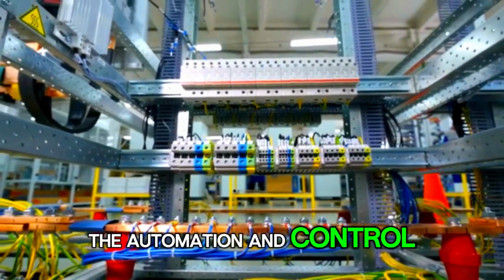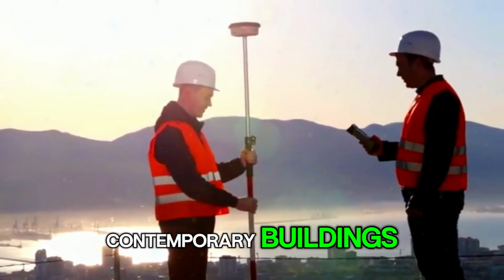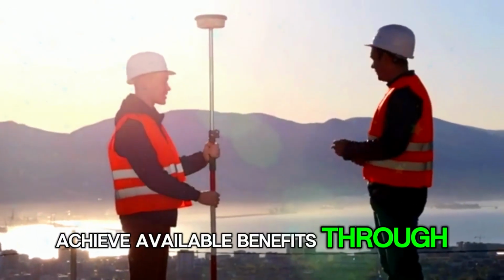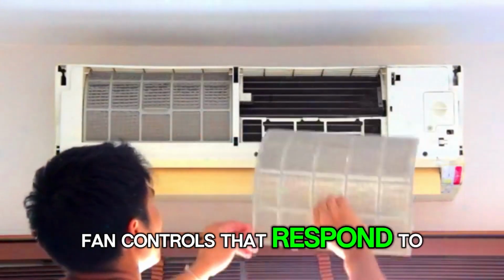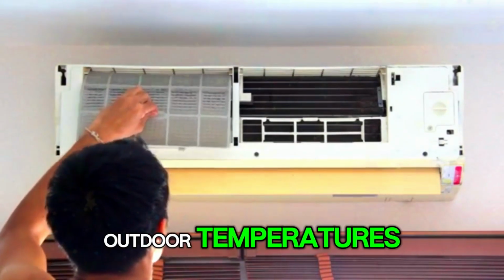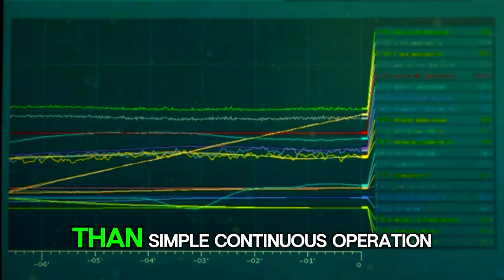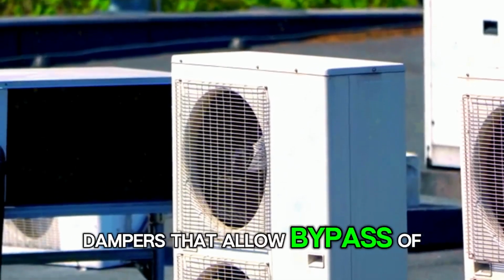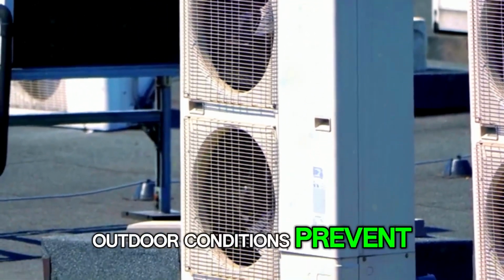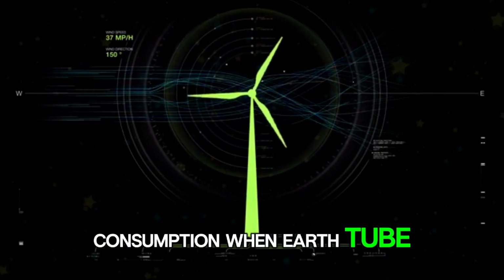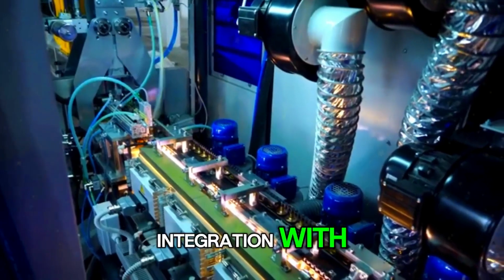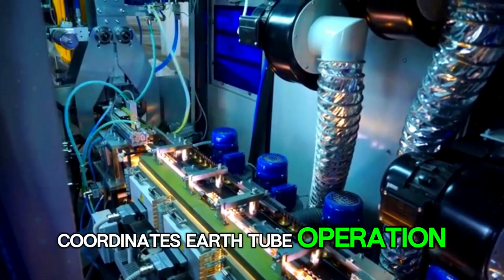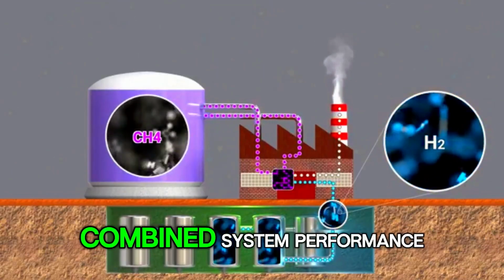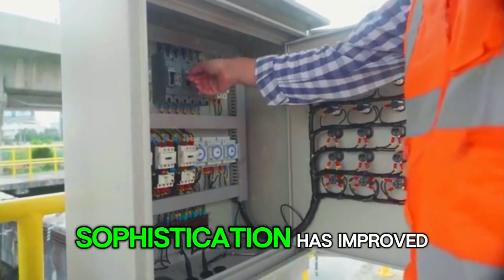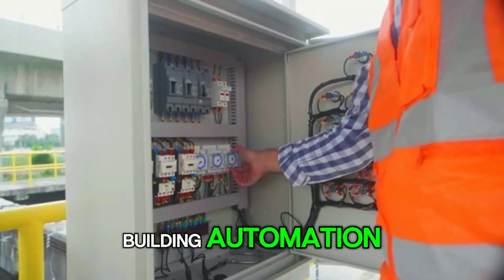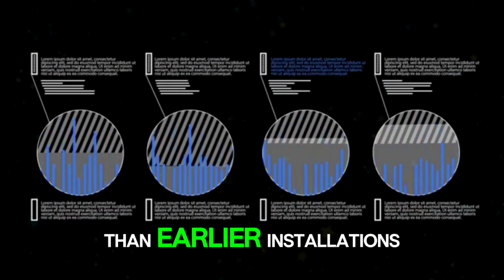The automation and control considerations for earth tube systems in contemporary buildings determine whether installations achieve available benefits through intelligent operation. Fan controls that respond to conditions inside pipes, outdoor temperatures, and indoor air quality produce better performance than simple continuous operation. Dampers that allow bypass of earth tubes during favorable outdoor conditions prevent unnecessary fan energy consumption when earth tube conditioning isn't beneficial. Integration with building automation systems coordinates earth tube operation with other HVAC functions for optimal combined system performance. The automation sophistication has improved substantially with contemporary building automation platforms, enabling better performance than earlier installations achieved with simpler control approaches.